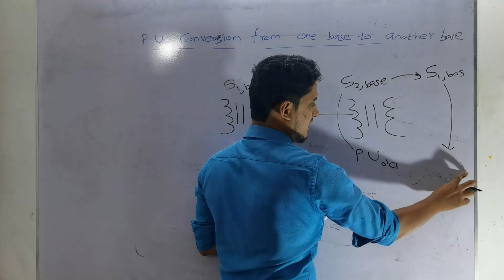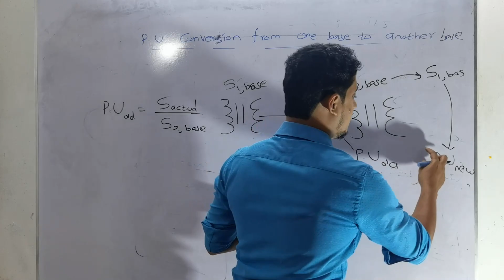So the old per unit is equal to the transformer's actual power divided by the transformer's base value, which is S2 base value. Now we will convert the per unit for S1 according to the S1 base. So the new per unit is equal to S actual divided by S1 base value. This is the new per unit, and the old per unit was defined with S2, while the new per unit is defined with S1.